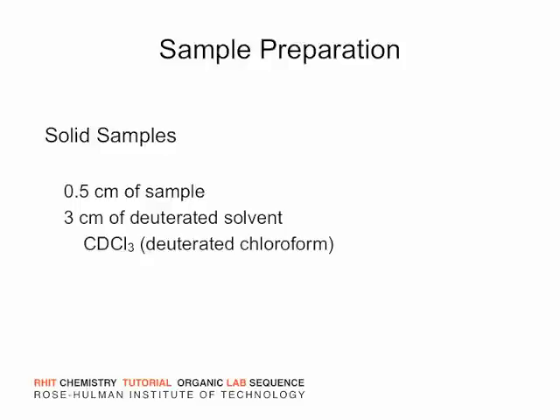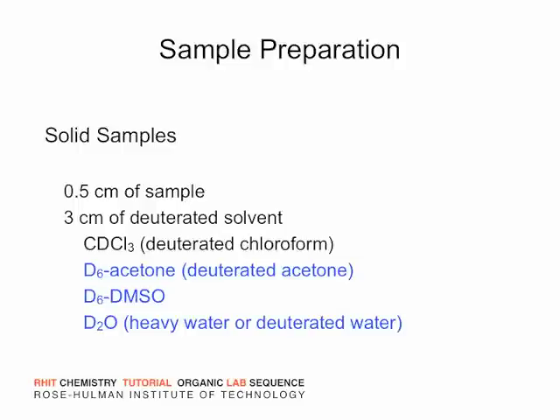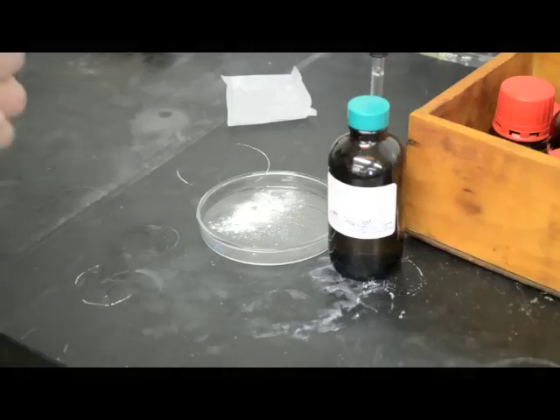When running an unknown sample, test the solubility of the compound in the normal solvent first before using the more expensive deuterated version. If the sample is not soluble in chloroform, you might be able to use deuterated acetone, deuterated DMSO, or deuterated water. However, all of these solvents result in somewhat greater problems with interpreting the spectral data.